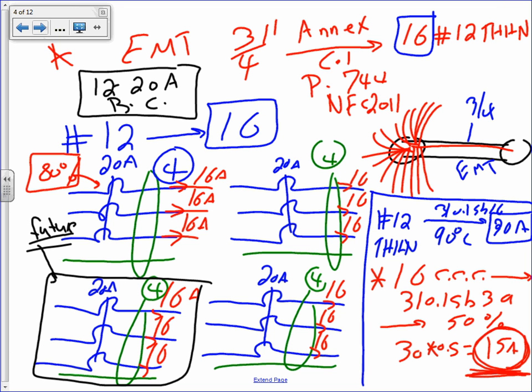If you guys understand this, you will understand the 3-phase circuiting completely. So I have 3 20 amp circuits tied together, 3 20 amp circuits tied together, 3 20 amp circuits tied together, 3 20 amp circuits tied together. These are multi-wire branch circuit 1, multi-wire branch circuit 2, multi-wire branch circuit 3, multi-wire branch circuit 4. All of them are grouped in a 3/4 of an inch conduit here. And I know these are 16 conductors. Have I maxed my conduit? Yep, I maxed my conduit. I didn't exceed it. So conduit fill, I'm good.